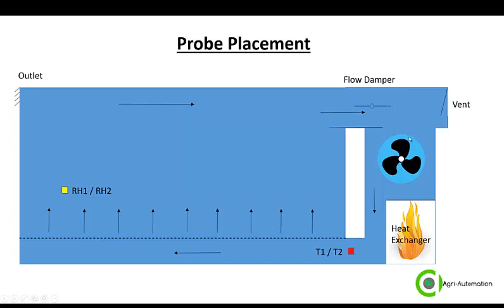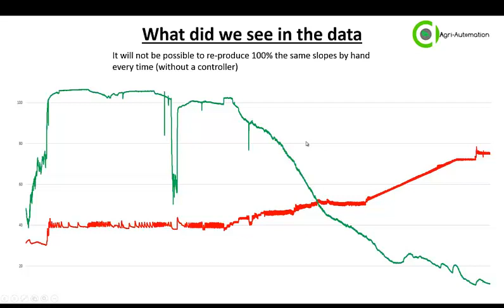So basically, what did we see in the data? It will not be possible to reproduce 100% the same slopes by hand every time. If you see this relative humidity slope is all over the place. Now the next dry run to try and get that same slope will be impossible. So this is a slope done by hand, and this slope is what our controller produced. So the blue line is the target of the relative humidity, the orange line is the target of the temperature, and this red line is the actual temperature, and this green line is the actual humidity. So as you can see, the green line follows the blue line, and the red line follows the orange line.